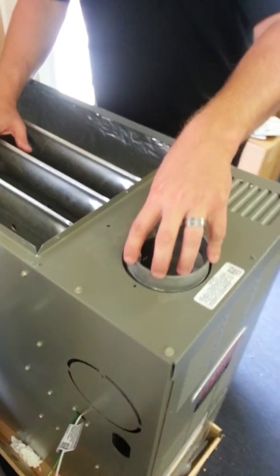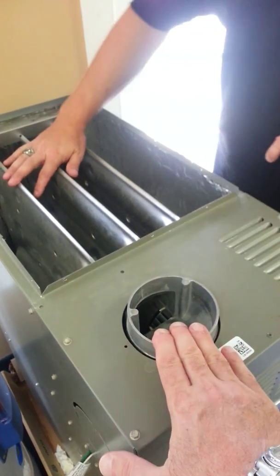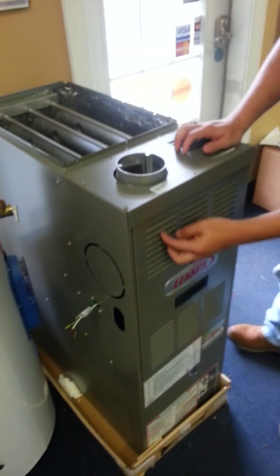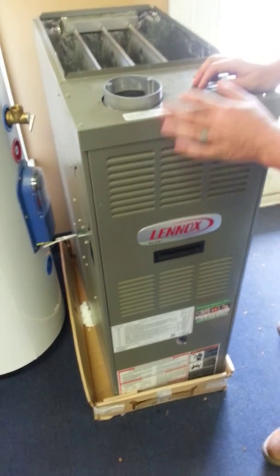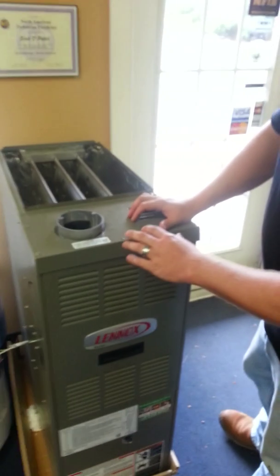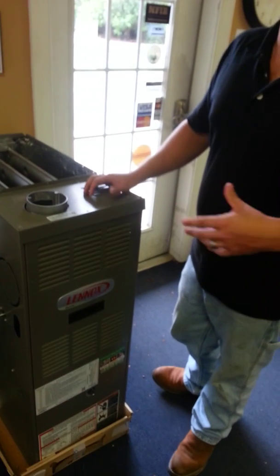This one, being 80%, uses B-vent metal exhaust - that's where the B-vent attaches. All these ridges are your fresh air intake. Depending on your local code, this one requires fresh air, either from a large room...